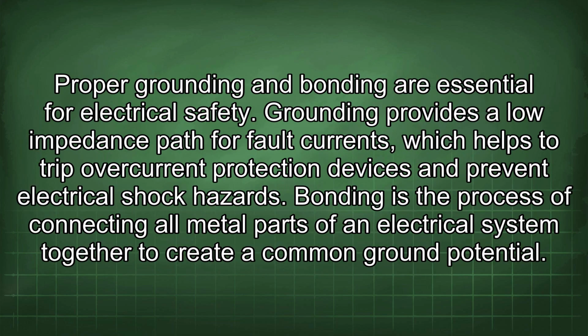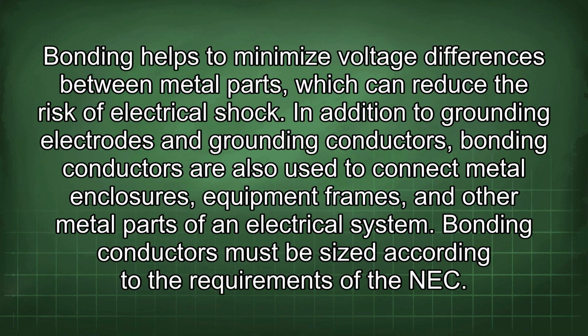Proper grounding and bonding are essential for electrical safety. Grounding provides a low impedance path for fault currents, which helps to trip overcurrent protection devices and prevent electrical shock hazards. Bonding is the process of connecting all metal parts of an electrical system together to create a common ground potential. Bonding helps to minimize voltage differences between metal parts, which can reduce the risk of electrical shock.